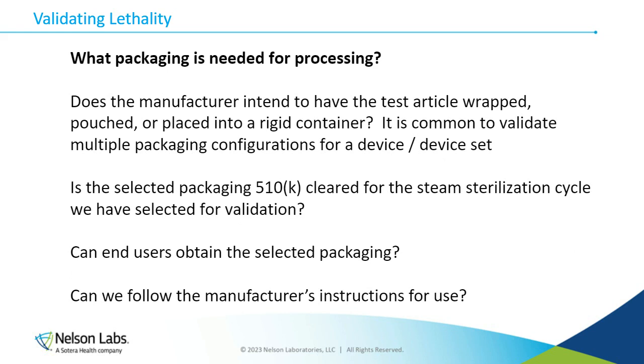We need to decide what packaging to use during validation, which will be included in the device instructions for use. Does the manufacturer intend to have the test article wrapped, pouched, or placed into a rigid container? Sometimes we see a combination. It's very common to see a test article set that is wrapped and also placed into a rigid container as two separate packaging options, and it is common to validate multiple packaging configurations. The selected packaging must be 510(k) cleared for the particular sterilization cycle, and end users must be able to obtain the selected packaging when following the manufacturer's IFU.